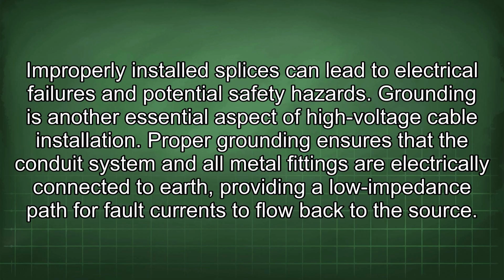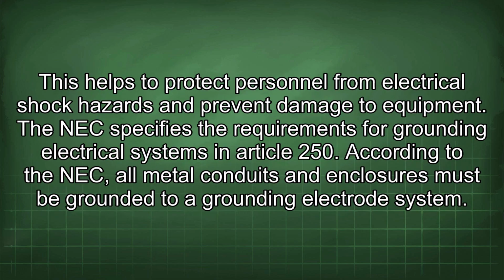Grounding is another essential aspect of high-voltage cable installation. Proper grounding ensures that the conduit system and all metal fittings are electrically connected to earth, providing a low-impedance path for fault currents to flow back to the source. This helps to protect personnel from electrical shock hazards and prevent damage to equipment.